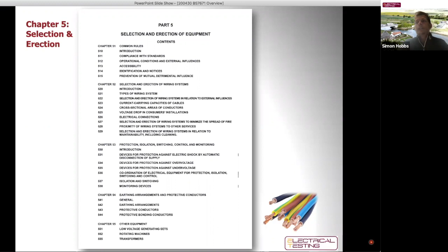Good, okay, so on to part 5. Part 5 is entitled Selection and Erection of Equipment, and this is where the regulations actually get into building your electrical installation. Through parts 1 to 4 we've effectively got into the design - we've chosen the protection we're going to use, the fuses, the breakers, and designed the maximum demand. We're now into selecting the actual equipment we're going to use and how we're going to install it. So the first thing in part 5 is chapter 51, what's called common rules.